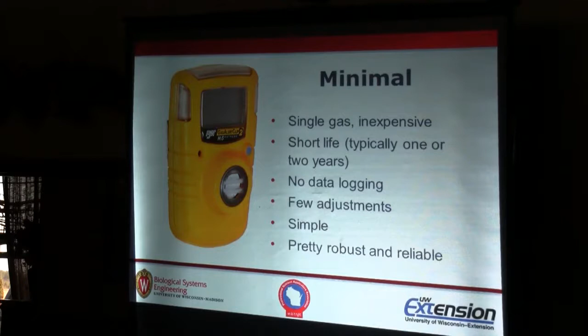The cheap one, the $130 one I'd probably go for, won't let me log data, won't have a lot of adjustments. It'll give me a low alarm condition and a high alarm condition - pretty simple, but also pretty reliable. These things are pretty dependable. They don't work instantaneously, they're not pumping, you're not drawing air into it like you would with the 4-gas. It's relying on diffusion, so you might have a lag time of 10, 20, 30 seconds or more.